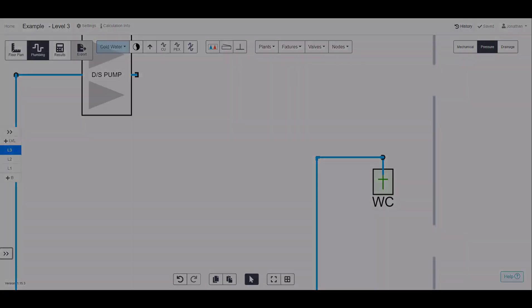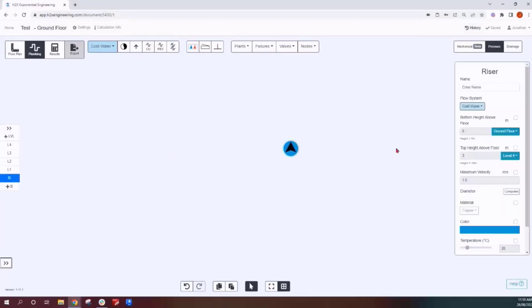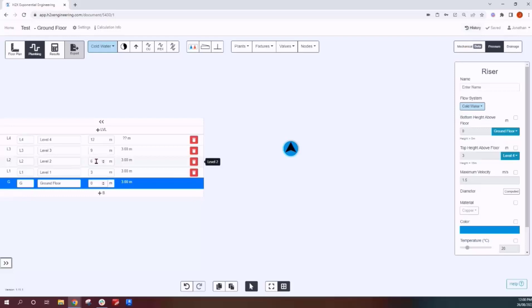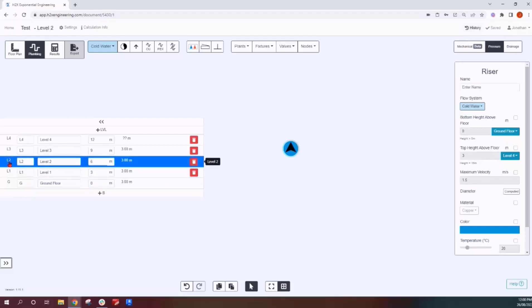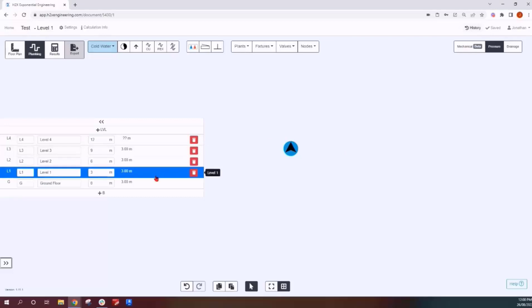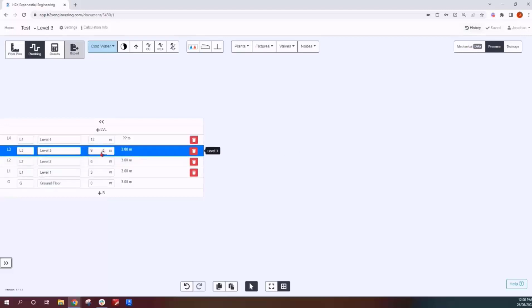If you add a riser it will default to the bottom of the ground floor to three meters above the top floor, and you can control the height of each level. If you want to offset a riser on level two — say at 8.7 meters, which is 2.7 meters above level two — set the top height of the riser to 2.7 meters above level two. Below that height the riser shows; above it, it stops.